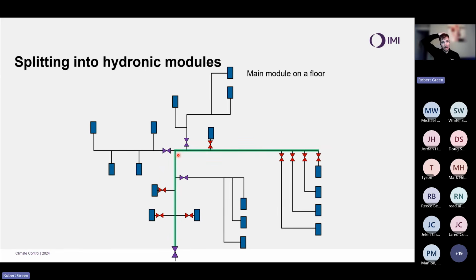And you'll notice in this example, we've got 3 valves that are also submodules. So we carry out the same operation on the submodules. In this case, it's really simple. My submodules just have terminal units, so we place the balancing valves on each of these terminal units. We do the same process here. And finally, we do this process at the end there. And we have now correctly identified the optimal number of manual balancing valves we need to manually balance this system in the most optimized way.